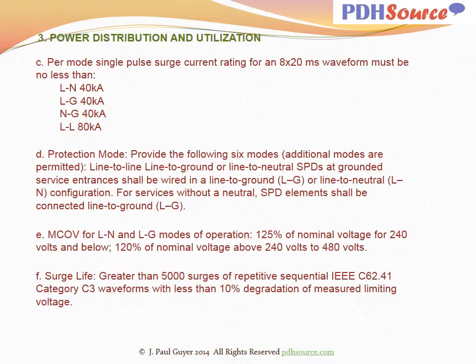MCOV for LN and LG modes of operation: 125% of nominal voltage for 240 volts and below, 120% of nominal voltage above 240 volts to 480 volts. Surge life, greater than 5,000 surges of repetitive sequential IEEE C62.41 category C3 waveforms with less than 10% degradation of measured limiting voltage.